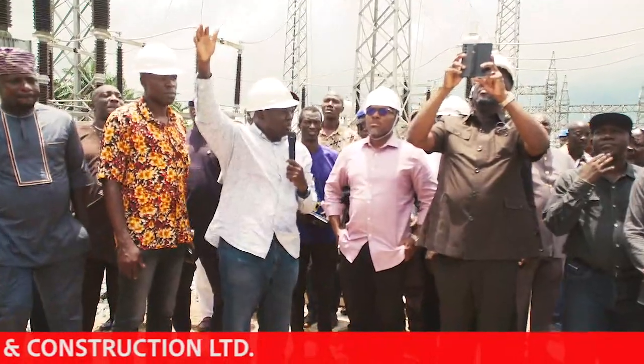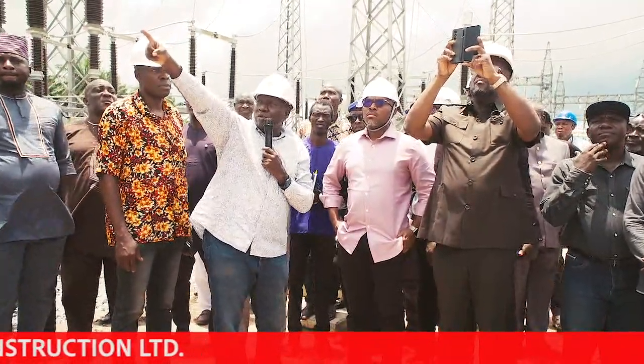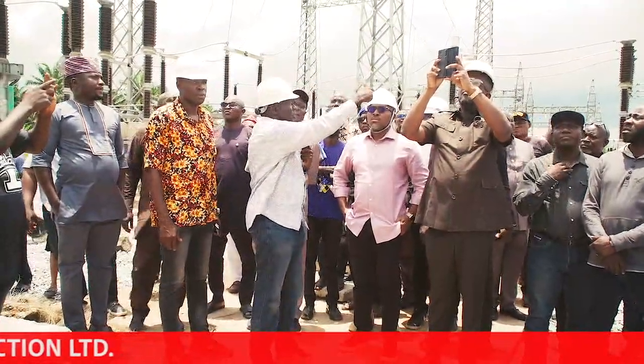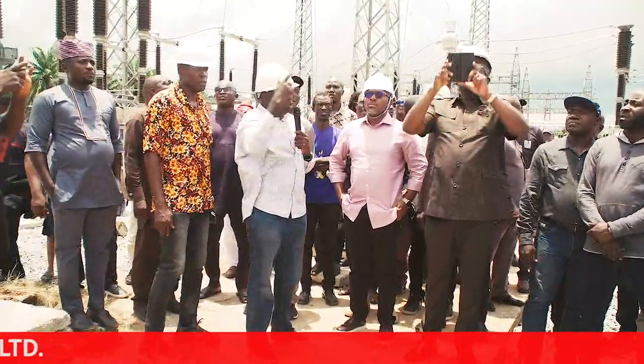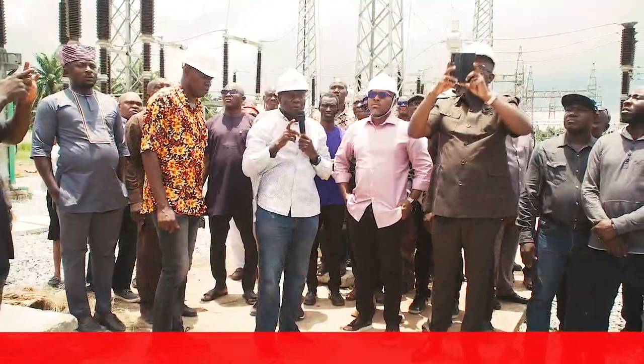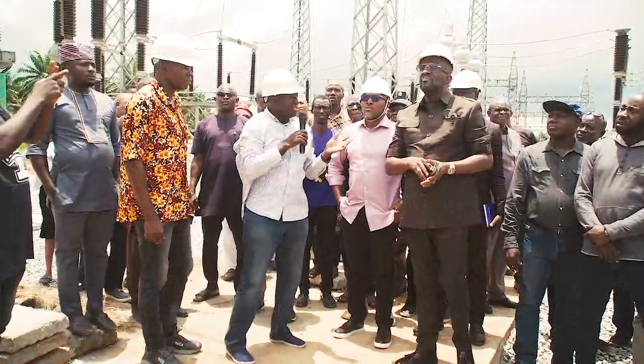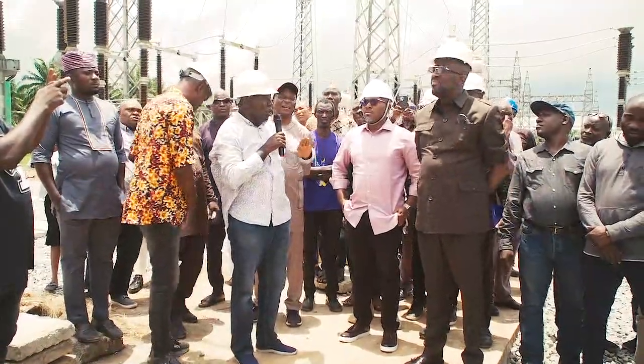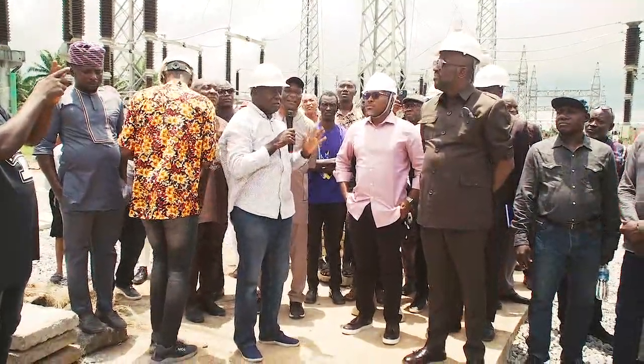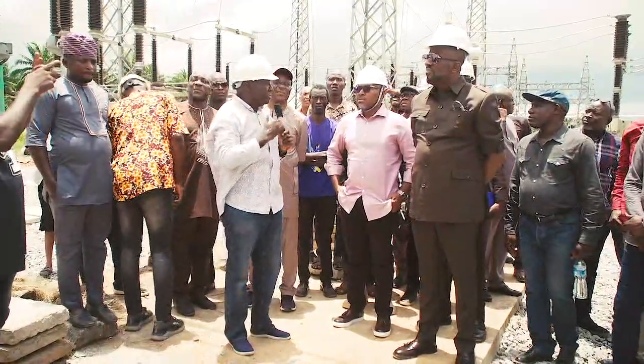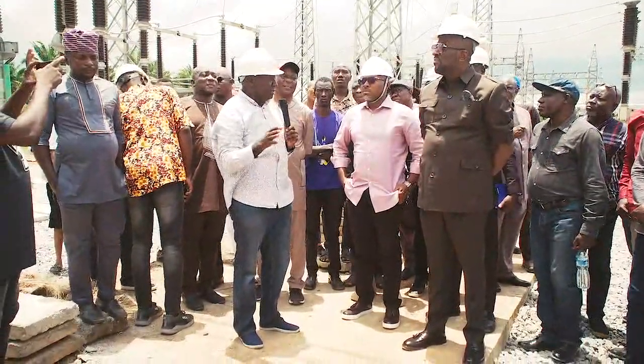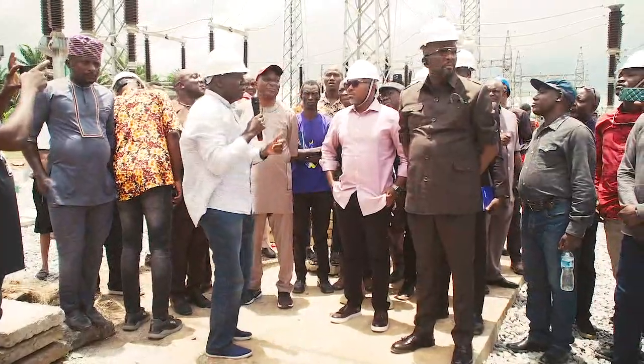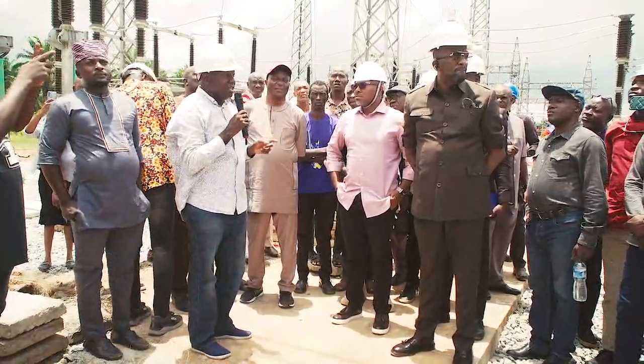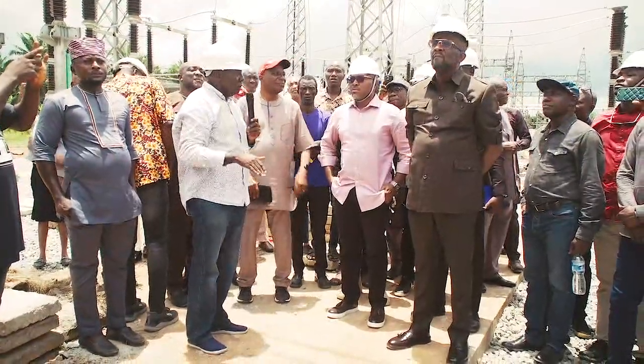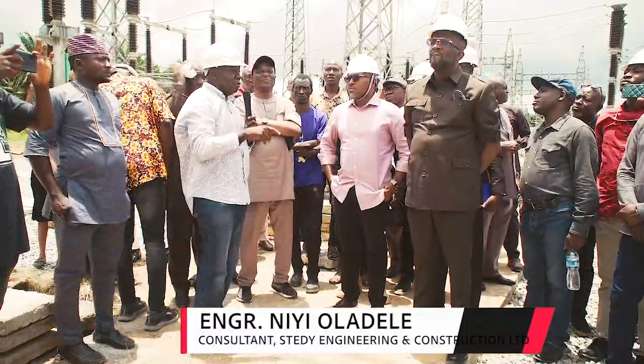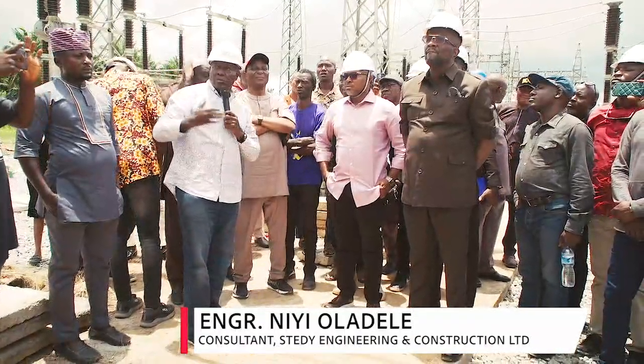As soon as the motor station is ready to energize, we have those lines coming straight to this transformer. Each of the transformers is a 30 by 40 MVA transformer. 30 because it can deliver 30 on natural loading, 40 when it is forced with air, it will deliver 40 MVA. So the two of them combined will give us an aggregate of 80 MVA. So the Okitipupa substation is a 2 by 40 MVA substation.